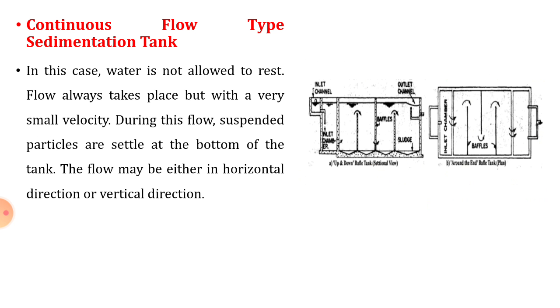Then continuous flow type sedimentation tank. On the contrary, here the flow, as the name suggests, is continuous. In this case, water is not allowed to rest as in the fill and draw type. Flow always takes place but with a very small velocity. During this flow, the suspended particles are settled at the bottom of the tank. The flow may be either in the horizontal direction or vertical direction. As shown in the figure, baffles are provided, which are responsible for the reduction in velocity, so sufficient sedimentation or settling can be achieved, and the settled sludge is taken out and discharged from the tank.